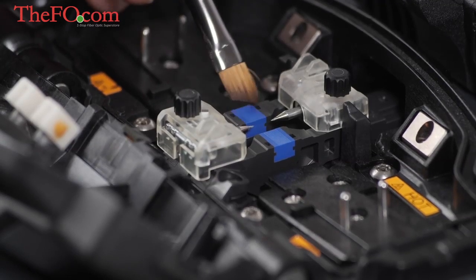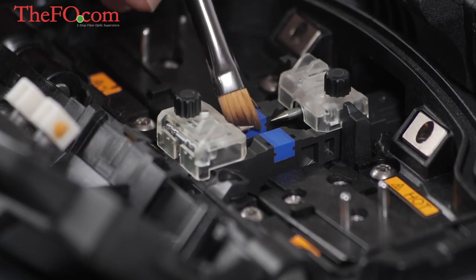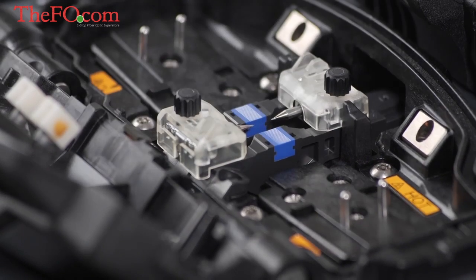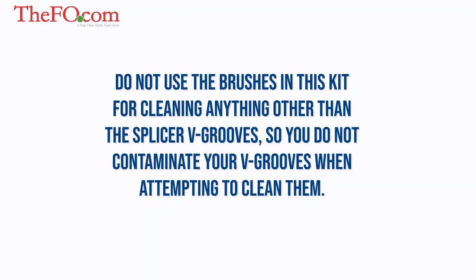Lastly, sweep a final time with the soft brush to remove any loose contamination that might have deposited during this process. Do not use the brushes in this kit for cleaning anything other than the Splicer V-grooves, so you do not contaminate your V-grooves when attempting to clean them.